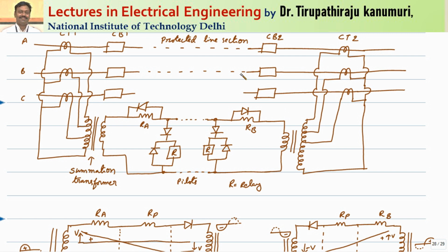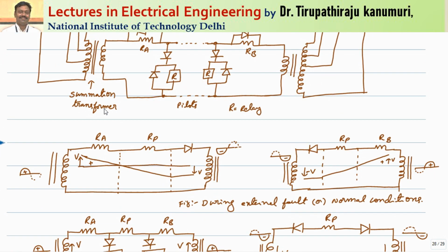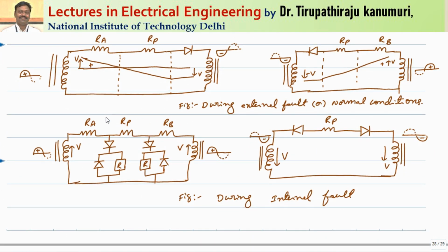Or the second case: the voltage at the sending end is full voltage, and the voltage at the receiving end will be reversed when compared to the previous value when it is a double fed system. Whenever it is a double fed system, the voltage at the receiving end will be reversed and the voltage at the sending end will be the same. If it is a single fed system, the voltage at the receiving end will become equal to 0 and the sending end will have some magnitude. So let us take the case of the double fed system. This is the worst possible case, so that's why I am discussing this one.